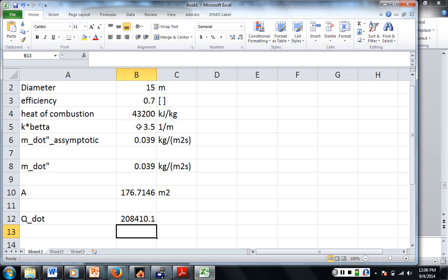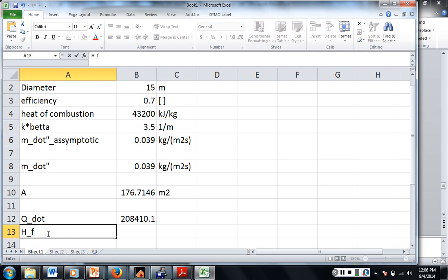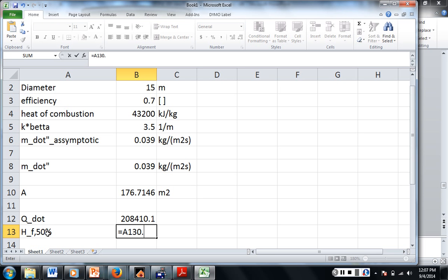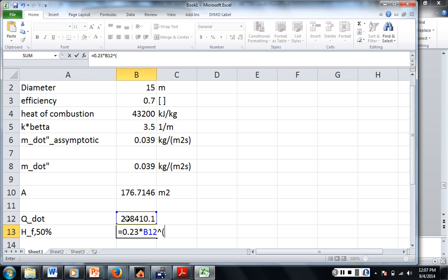And then the height of the flame, if we were to do the average height. So this is the height of the flame, 50%. I like to make a note, make sure everybody's aware. We're talking about the average height, not the consistent height, is equal to 0.23 times our heat release rate, raised to the two-fifths power. So to raise things to the power, use this carat symbol, and then parentheses around the two-fifths, otherwise it won't come out right. Alright.